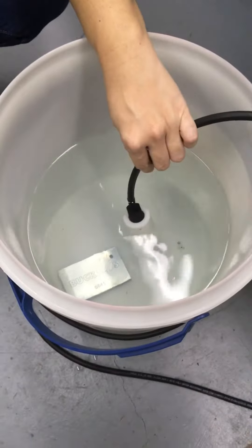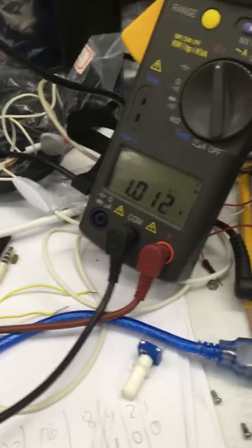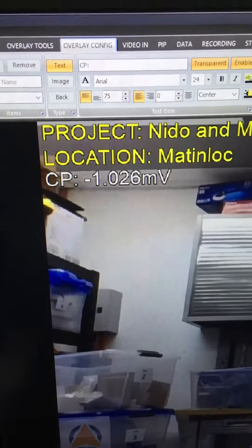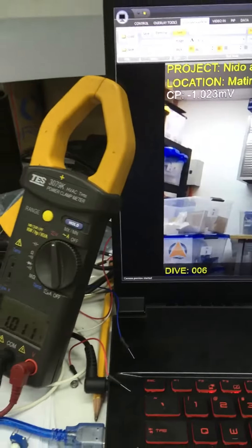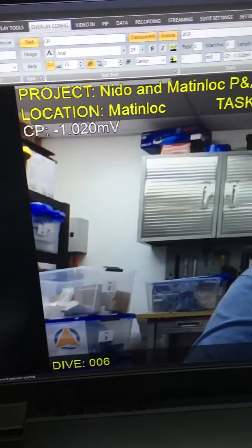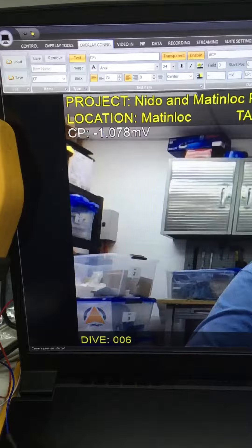Randy is going to stab the zinc block — try to push hard on it. We have the value here on the multimeter and the value showing on the ocean vault recorder. Right now there's about a 12 millivolt difference, which is acceptable, and I will improve the accuracy and the average of the display.